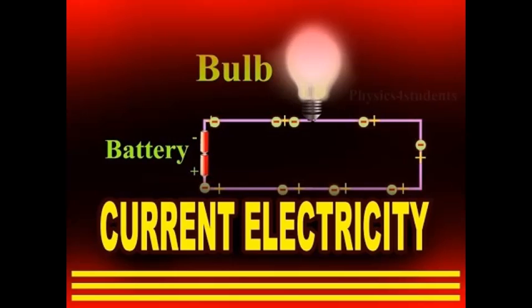So how will you decide whether you buy a 3 ampere, 1 ampere, or 13 ampere fuse? For that we need this particular calculation. The fuse rating must be higher than the current that normally flows through a device, but as close as possible to this value. We'll find out what amount of current is needed for a particular device, and choose a fuse very close to it, but a little higher.